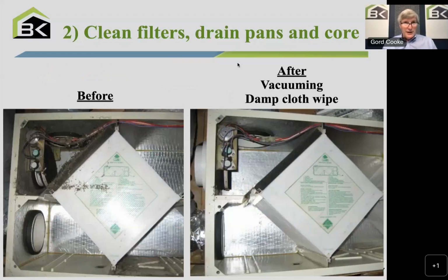Remember, we put on a bird screen. We didn't put on an insect screen. So in fact, there will be some insects inside the box. They're always in the fresh air airstream. I normally have the vacuum at hand and handy as I open up the unit. If there are any bugs flying out, I try to capture those right off the bat. But there's the top left. That's where most of the cleaning gets done.